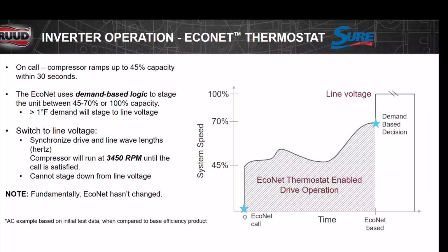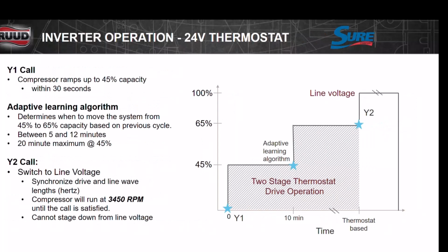Now, we call this a three-stage unit because if we put it with a thermostat, a regular 24-volt thermostat, then that changes the algorithm of what the board's going to do. We go from 0 to 45% in 10 minutes. Okay? So bam, for 10 minutes it's running here. After that it's running here, 65%. And then after that it goes up to 100%. So we get off the inverter at this point. There's first stage, second stage, third.